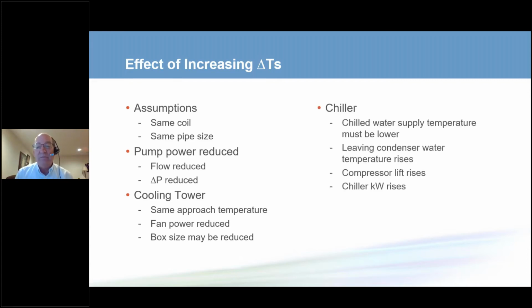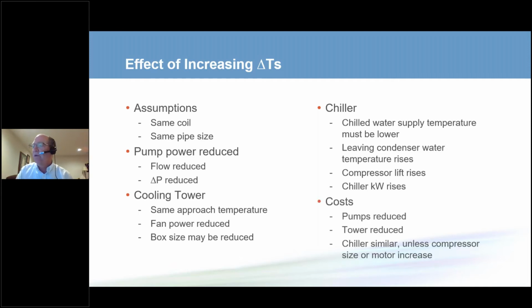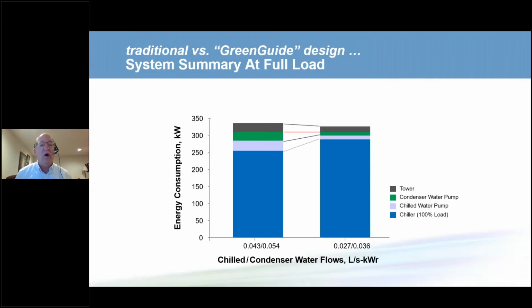The chiller. When we do this with a chiller, we're going to use essentially the same chiller. However, if we're going to use the same coils, we have to send that coil colder water. Therefore, the chiller's leaving chilled water temperature must be lower, which means the chiller will use more power. On the condenser water side for the chiller, the leaving condenser water temperature and the entering tower temperature are higher. So again, the chiller power goes up. The chiller must use more power, but the cooling tower and the pumps use less power. So if we look at this from a system standpoint, from a cost standpoint, our pumps are smaller, less costly. Our cooling tower has reduced cost, and the chiller is the same cost unless the compressor size had to get larger. So this is a lower installed cost system.